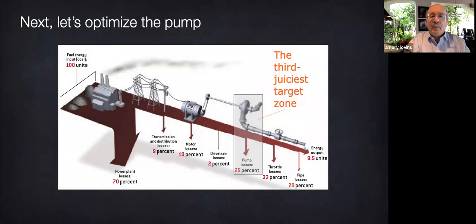Okay, now that we've minimized flow and friction, it's time to go further upstream and optimize the pump. But first, let me insert a remark about the buildings lectures example of purely radiant cooling in Singapore. It's a remark I couldn't make back then because you hadn't yet seen this diagram. Most people who are asked to save Singapore air conditioning energy will start by seeking a better air conditioner. That's like seeking a more efficient pump. It's worthwhile, but only after you have captured the higher leverage savings further downstream and shrunk or eliminated the air conditioner. So for thermal comfort, start with how much you need and how it's delivered.